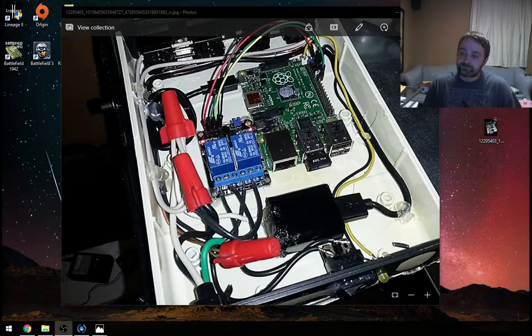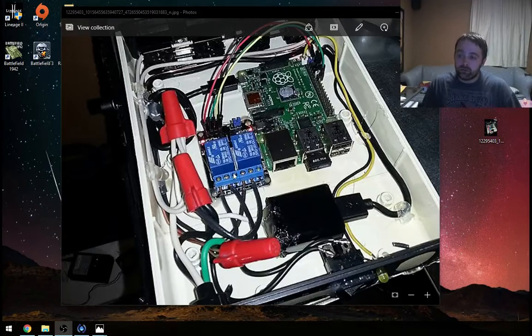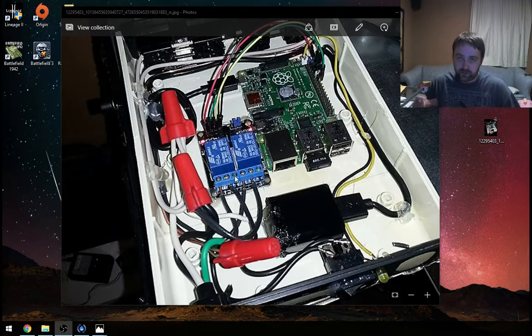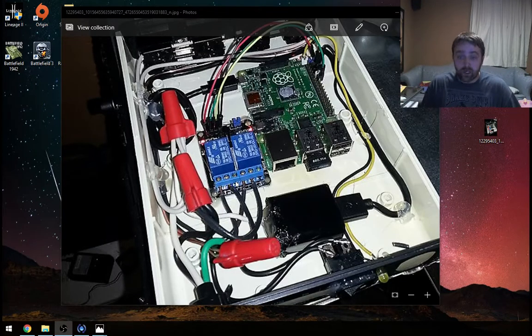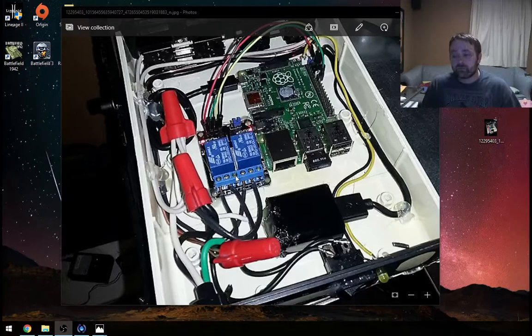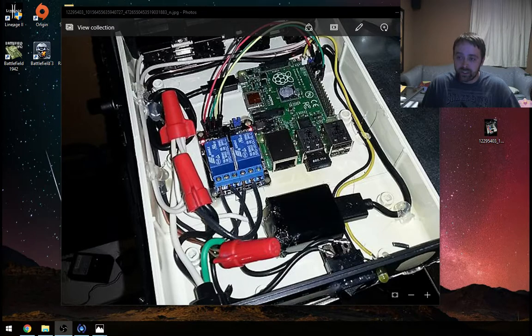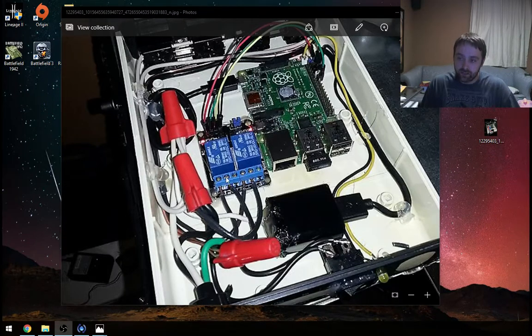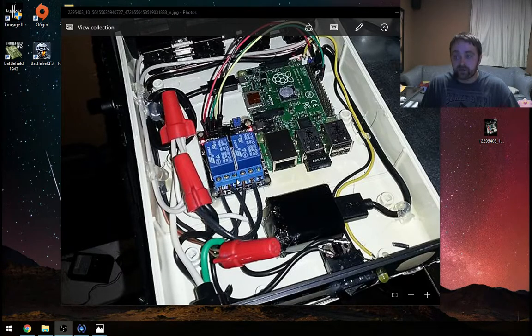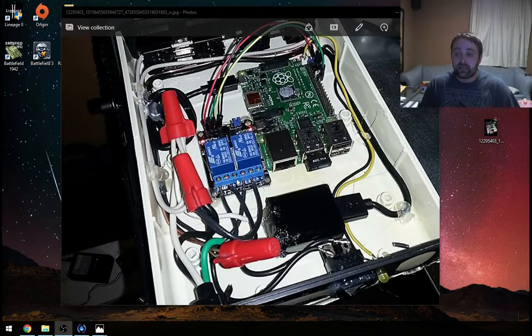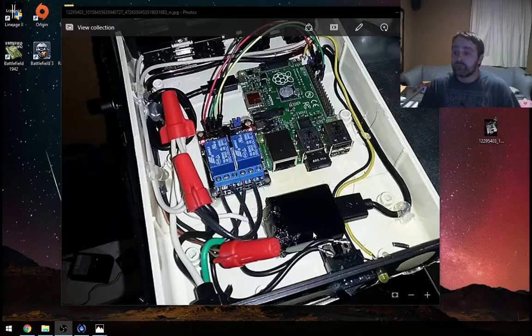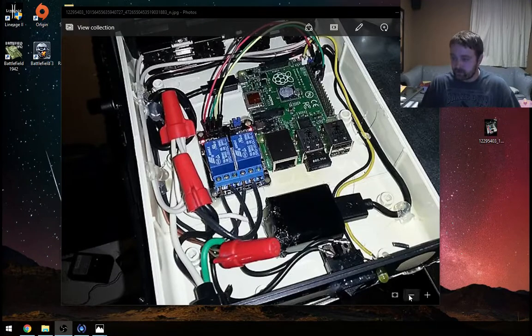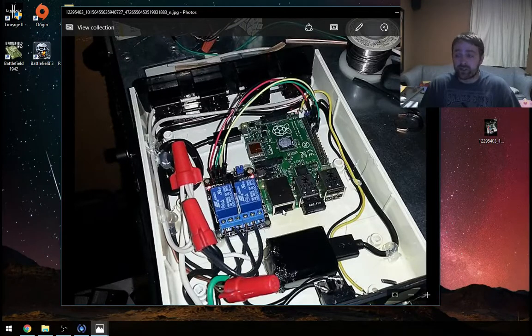So this is your supply. And it's the same on both of them. So you don't use this pin. Just screw it in tight. Don't stick a wire in there, because it will be the normally connected port. So if you do have anything plugged into there, this one is going to be live on both these center ports. That's your supply. So if you have anything plugged into this line here, that will be the normally connected. And basically it'll be a hot wire just sitting there doing nothing. So you want to make sure there's nothing in there. And that's pretty much it, at least as far as how it's all wired up. It's pretty simple. Again, it's basically the HVAC project all over again.